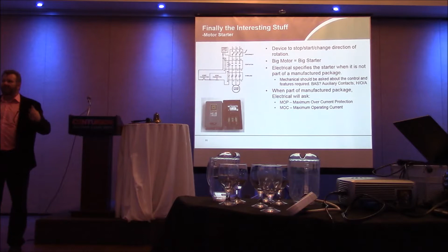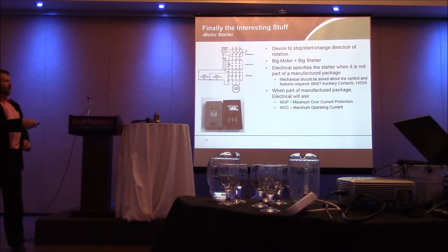Maximum operating current. What's the thing actually going to use? How many amps is it actually going to draw? MOP is always bigger than MOC. Sometimes not by much, but it's always larger. And typically, a cut sheet for a piece of equipment should have that on it.